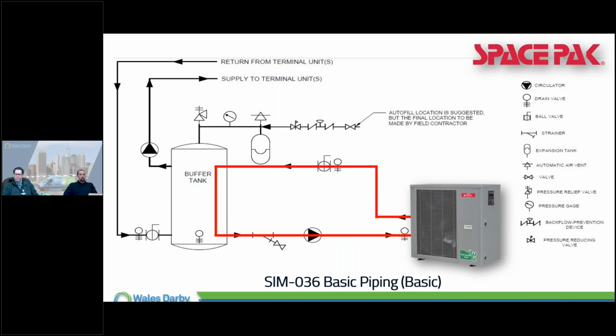Whatever it is, there's a cost, and then I say, why not put this elsewhere? The pushback I get is they don't want to see any equipment, they don't want to see the machine out there. Well, that's where we can be creative. You're only limited to your ability to size a pump to a pipe, really, that's all it is. I could put this thing 100 feet away, maybe in a remote area of the property, run some Uponor Ecoflex underground pipe, run that into the utility room or wherever the system's going to be, and now they don't see the outdoor unit.